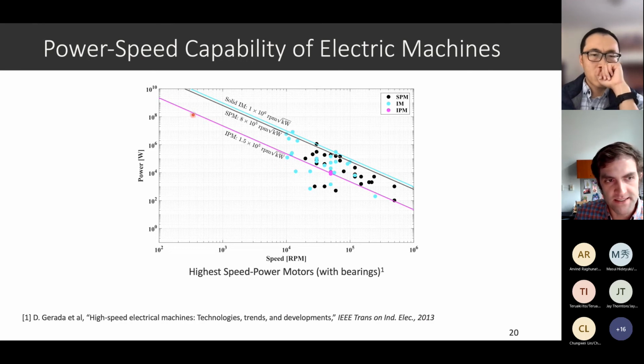This pink line here is the limit line for interior permanent magnet motors, and you can see that it has a lower speed power capability than surface-mounted permanent magnet motors. We kind of know this, right? If you put a carbon fiber retaining sleeve around magnets with a surface permanent magnet motor, you can achieve higher tip speeds, and therefore get a higher power rating.